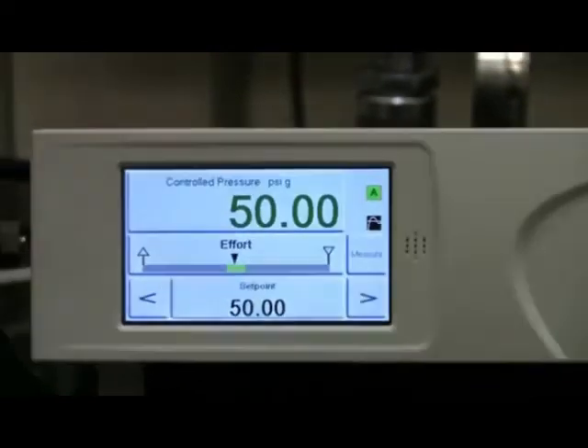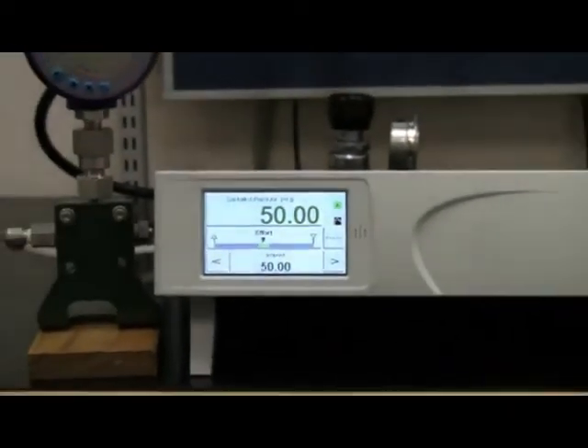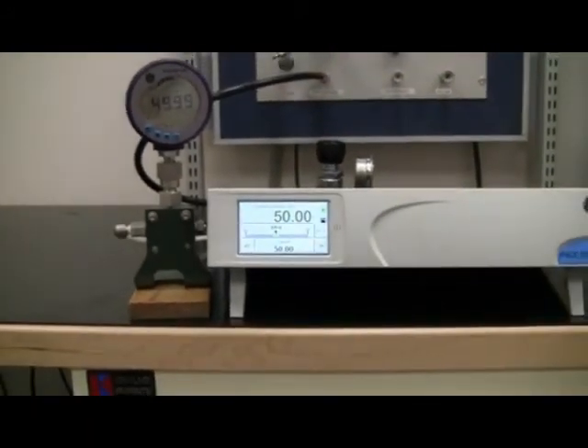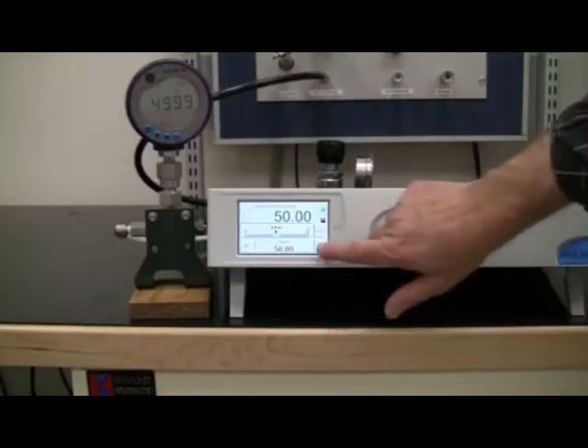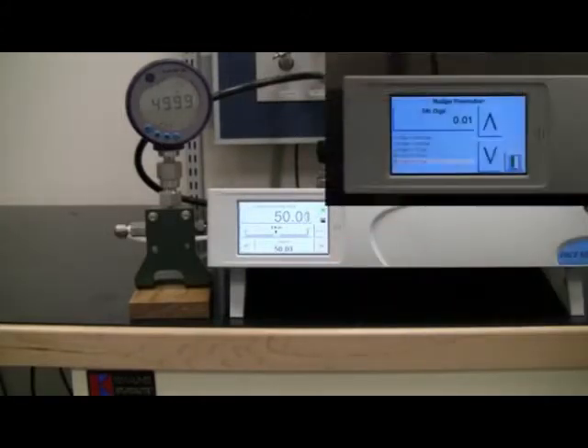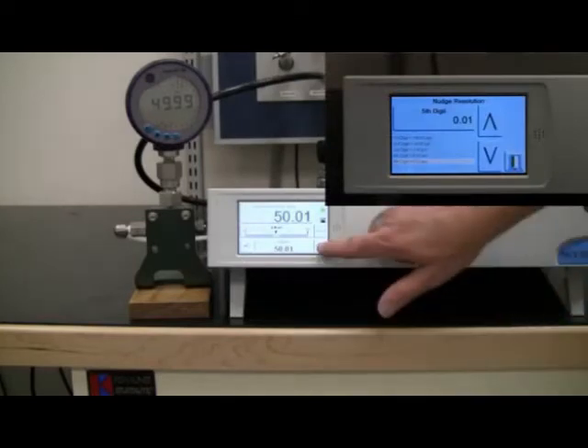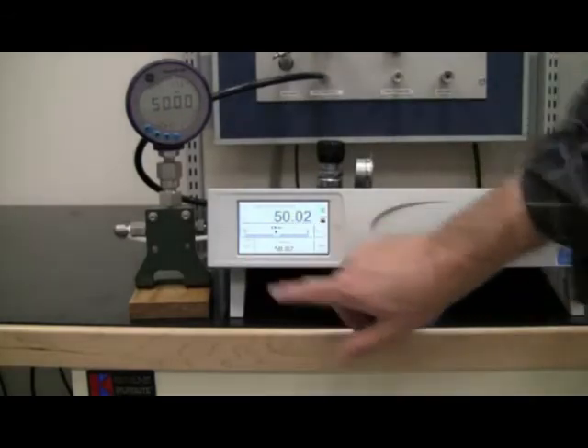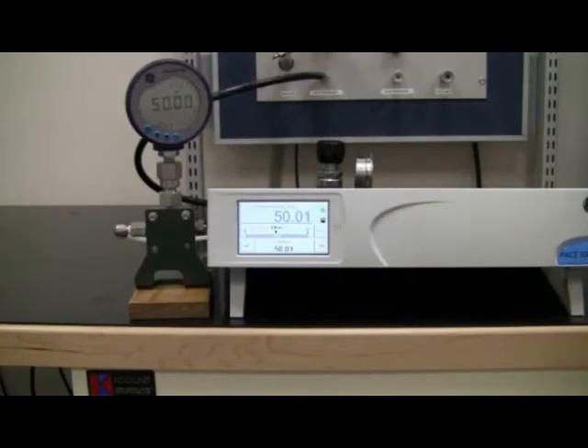We will now zoom out so we can see the pressure displayed on the device under test. If we prefer to be at a cardinal pressure reading on the device under test, we can use the nudge arrows to increase the pressure by a user defined magnitude. In this case, we set it to 0.01 psi. We can select the right arrow to nudge the pressure up so the device under test displays exactly 50.00 psi, and then compare this to the reading on the PACE 5000. The left arrow allows us to nudge the pressure in the downward direction.